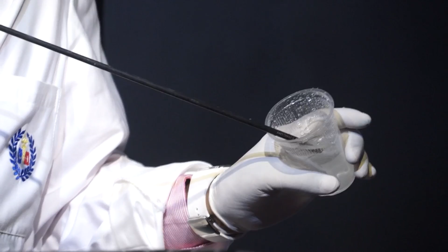55,000 vibration. If you touch it, it is cold. There is no heat as long as the fluid is there. If you want to cut dry tissue, some heat is produced, and it can seal a vessel up to 5 millimeter also. Electrosurgery can seal a vessel up to 3 millimeter, Harmonic 5 and LigaSure up to 7 millimeter. So suppose this is 5 millimeter here and you want to seal it, and I am using it here. Okay, press, and you see, coagulation.